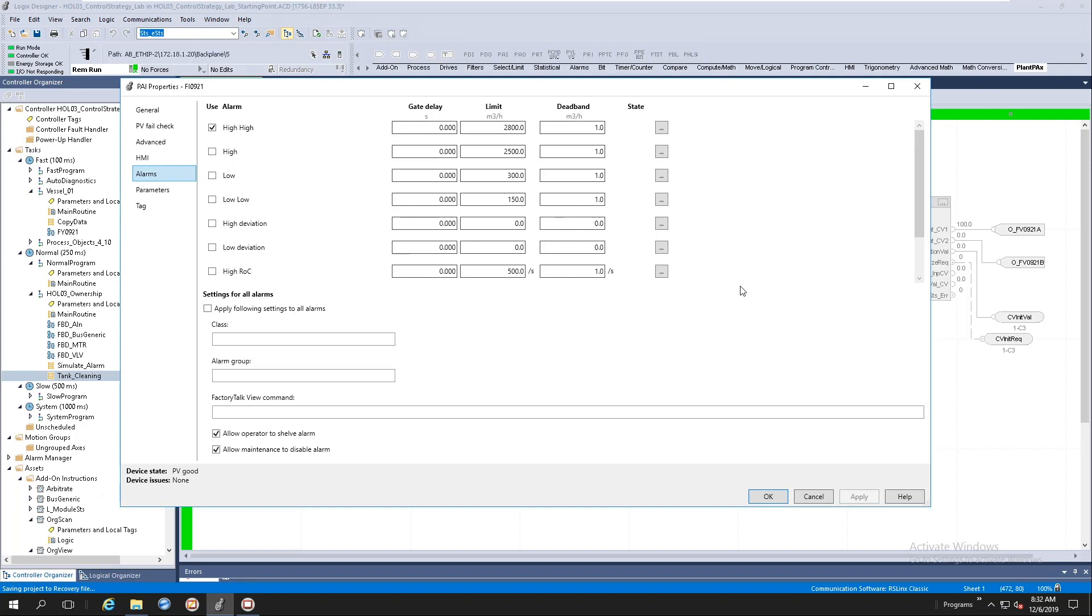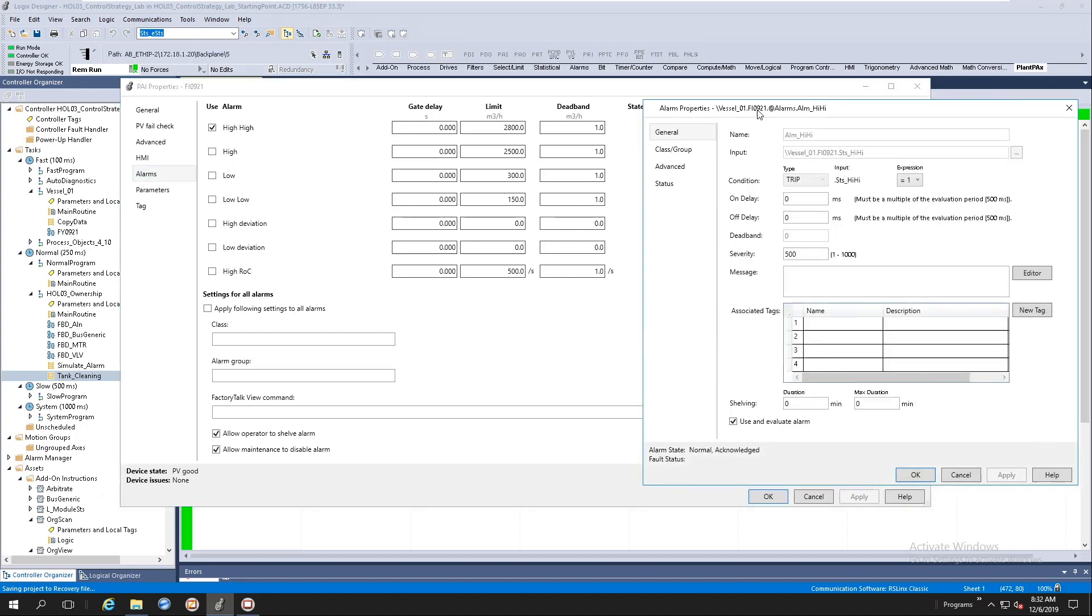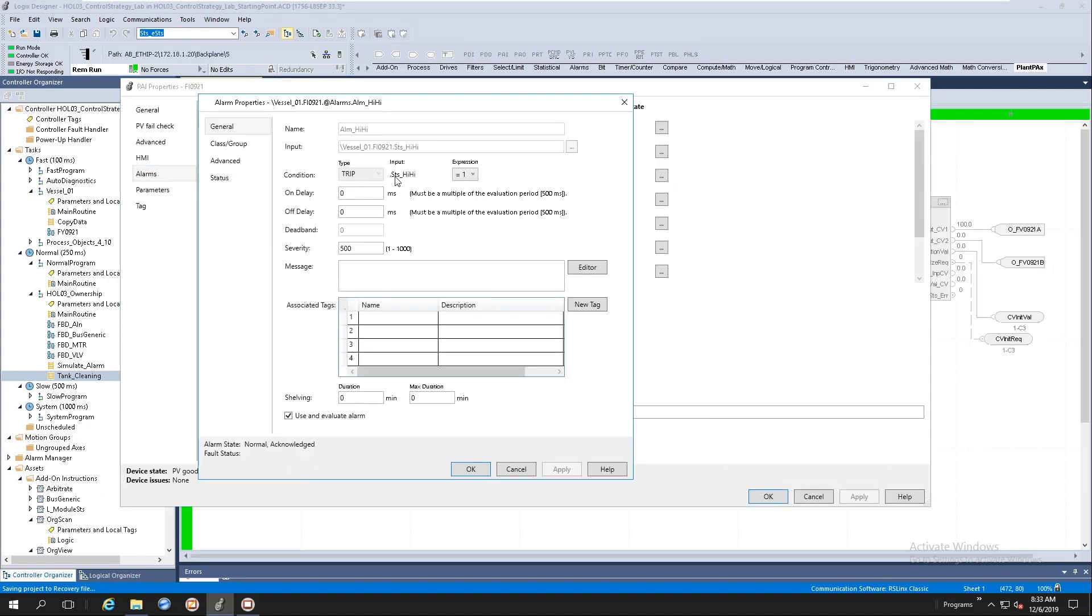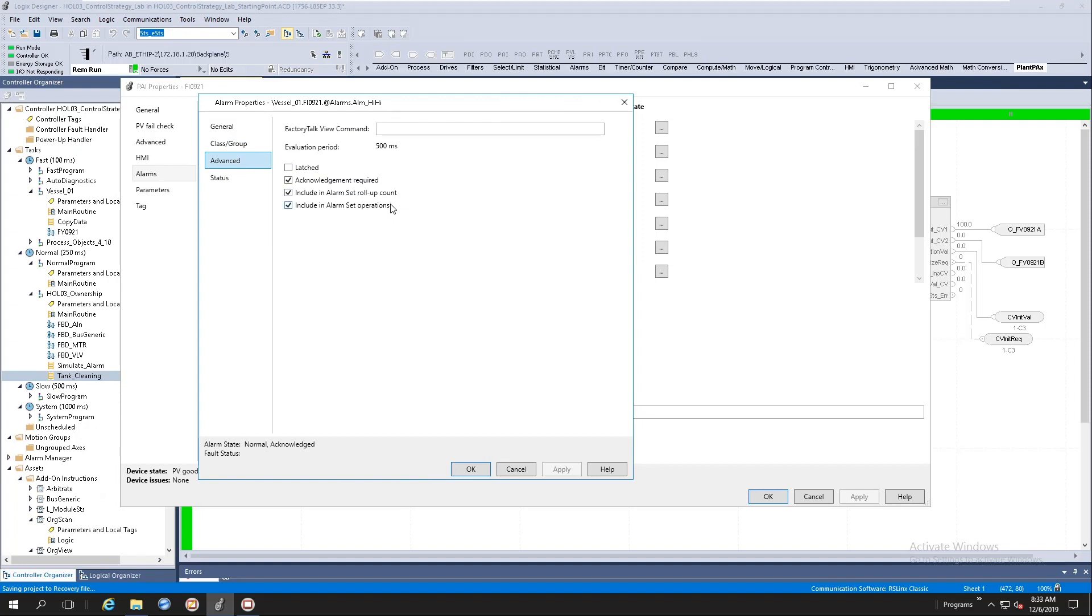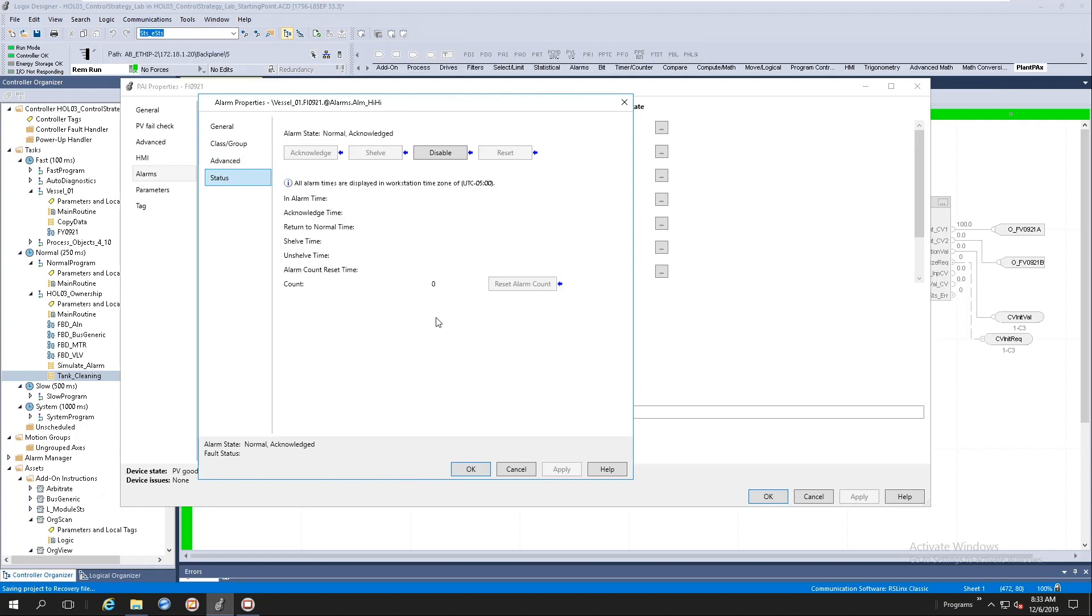All right, look here at the right hand side, we've got a thing called state here. If we click on the state ellipsis box, it will actually open up the logic tag-based alarm dialog property panel. Typical configurations that you'll get here are your on-delay, off-delay, severities, alarm messages, shelving durations, your class, alarm group. Do you want alarms to be latched? Do you want alarm sets to be rolled up? And do you want alarm set operations? And you'll get your status indicators here.